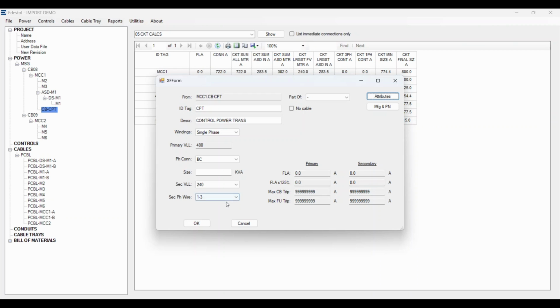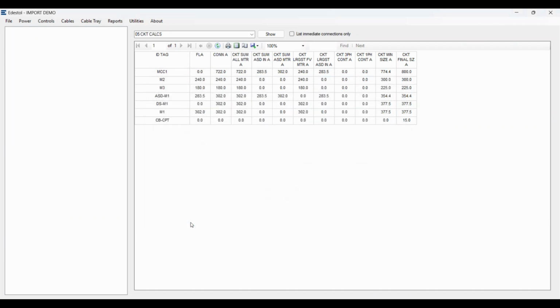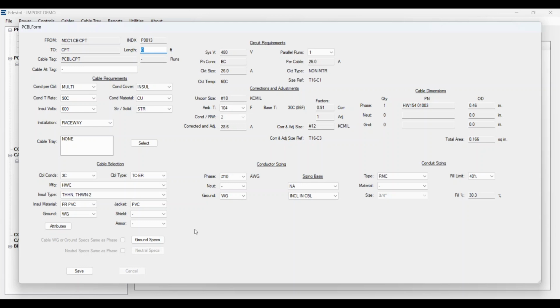We're going to feed it to a little distribution panel. And let's give it, I don't know, 10 kVA. Okay, so basically there's your primary FLA. Primary FLA times 1.25, and then your secondary FLA, and away you go. So max is the 60 on the secondary, max circuit breaker, max fuses there, depending on your size, things of that nature.